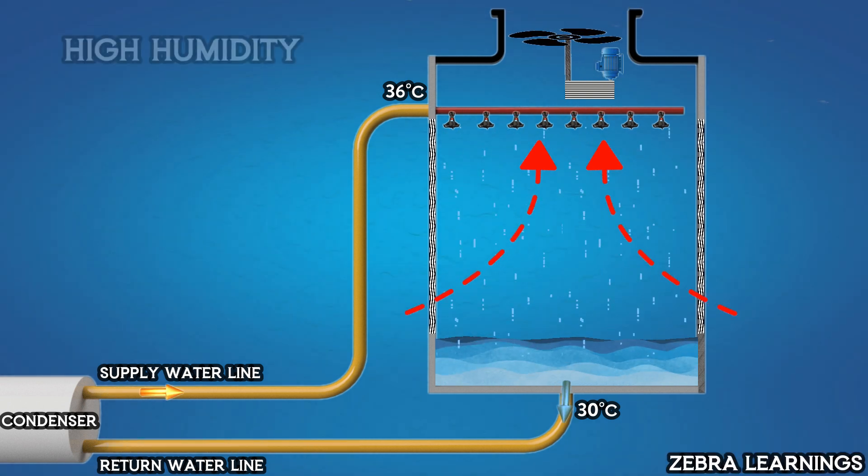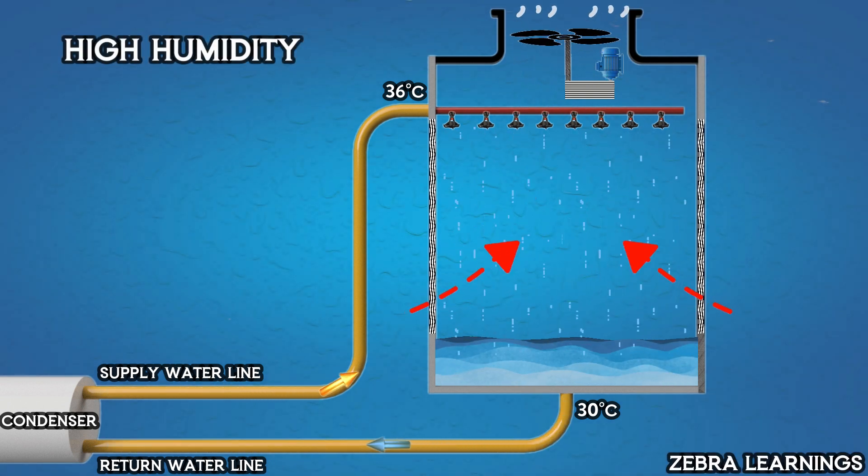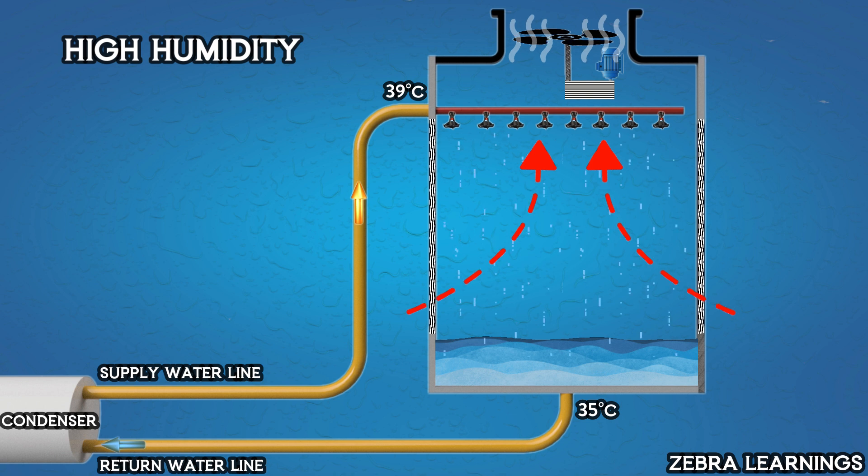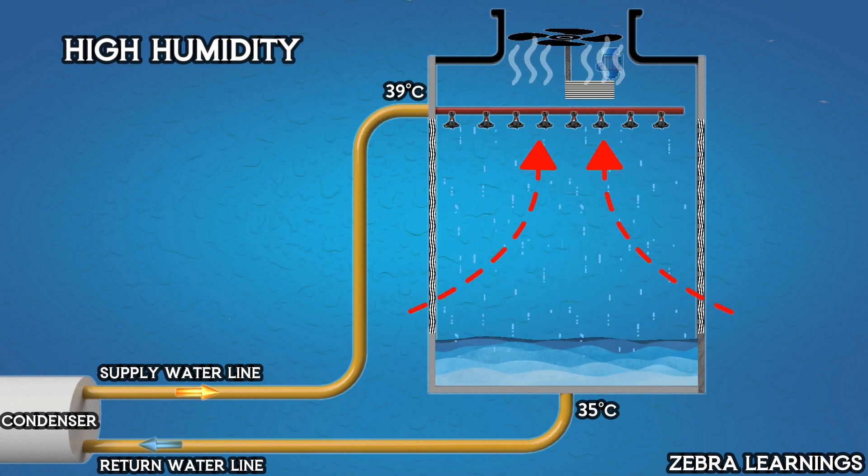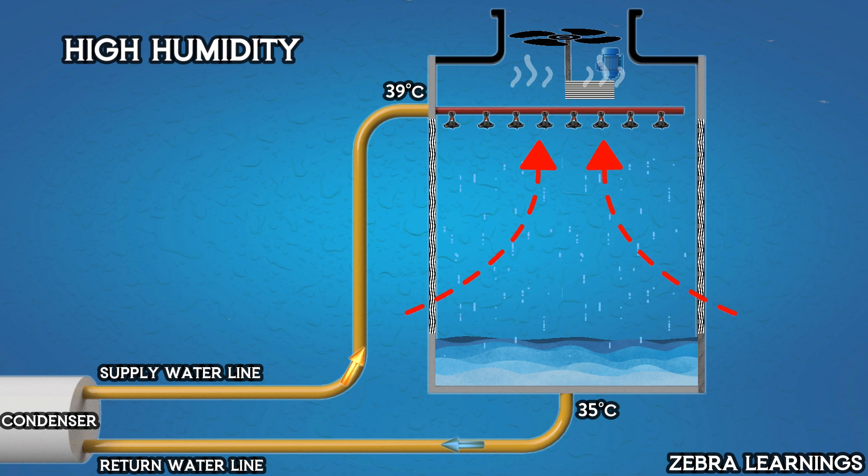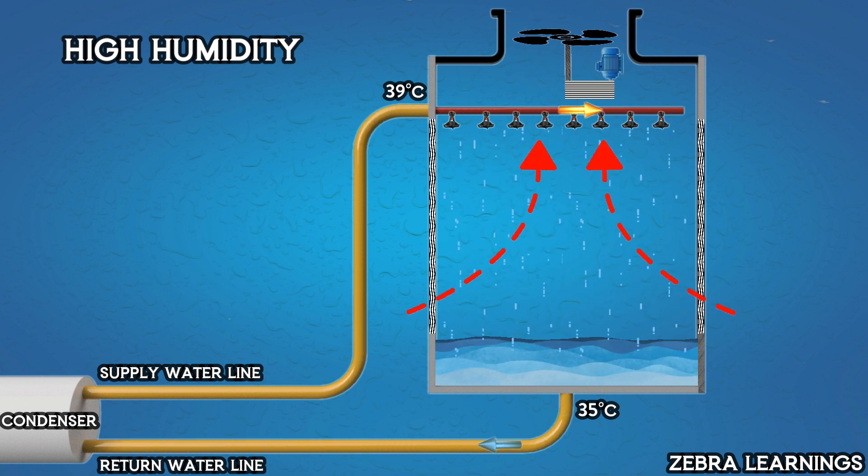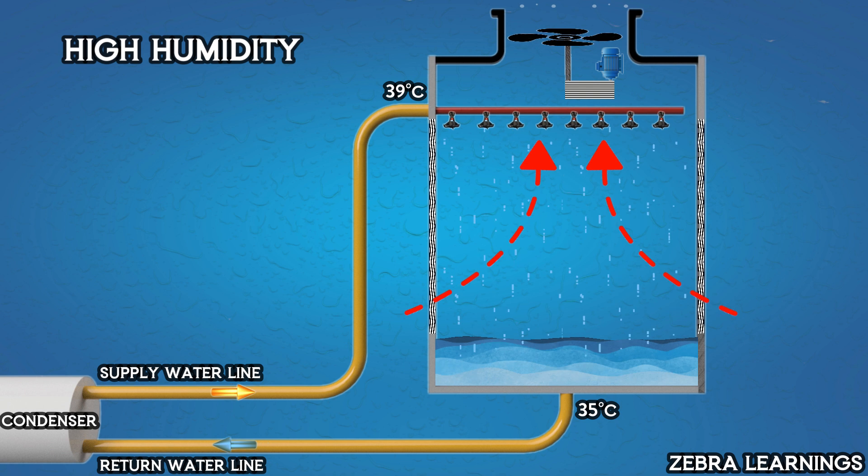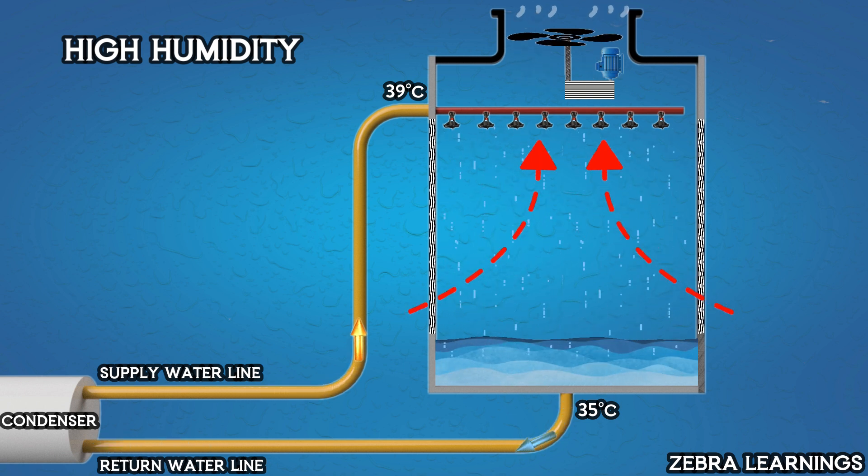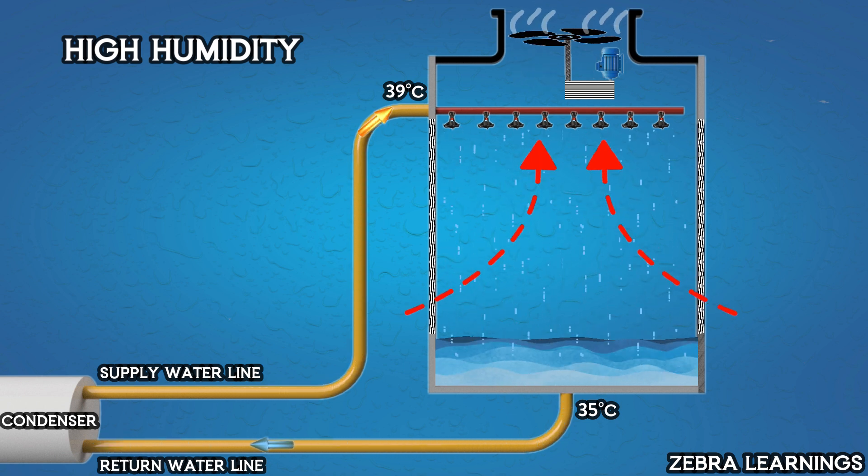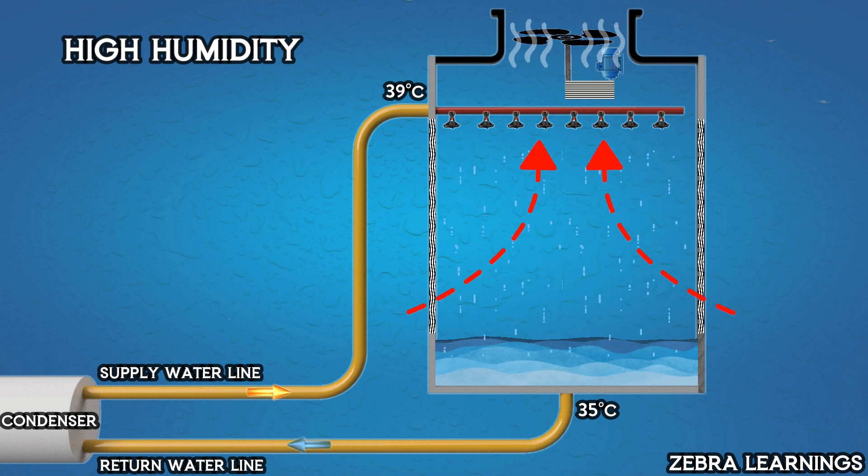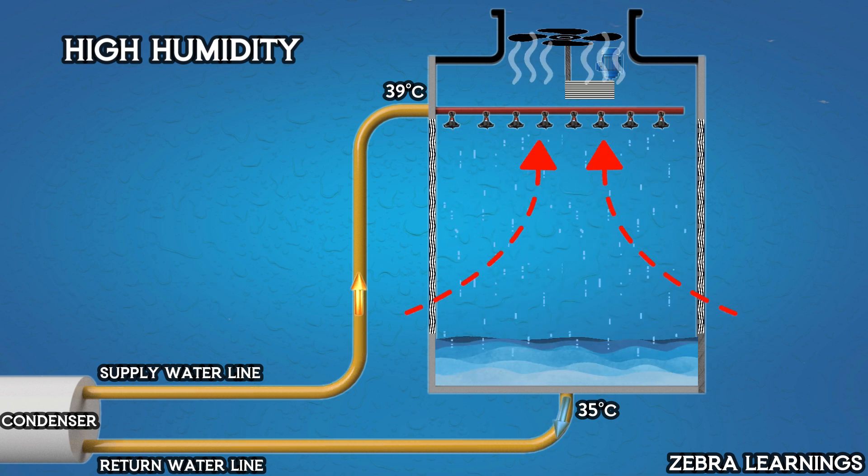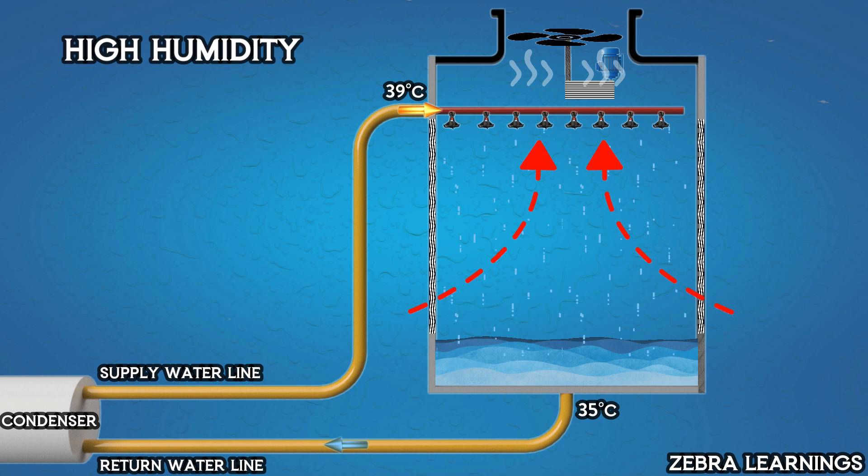However, when the humidity level is high, only less water evaporates from the cooling tower, and the water returning to the chiller is not cooled as effectively. This reduces the cooling tower's efficiency. Since the water entering the condenser is at a higher temperature due to the high humidity, it cannot cool the refrigerant as effectively. This leads to an increased load on the chiller. This is how high humidity affects the overall process of a chiller plant.